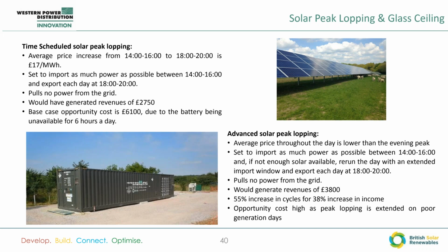So the system was set to export as much power as possible, solar power, not importing, between 2 and 4 p.m. and export it again between 6 and 8. And this would have generated revenues of £2,750 over the year, so we're not talking about huge amounts of money. And the base case opportunity cost is £6,100, so that's the battery being unavailable for 6 hours a day. That's a simplistic time-scheduled system.